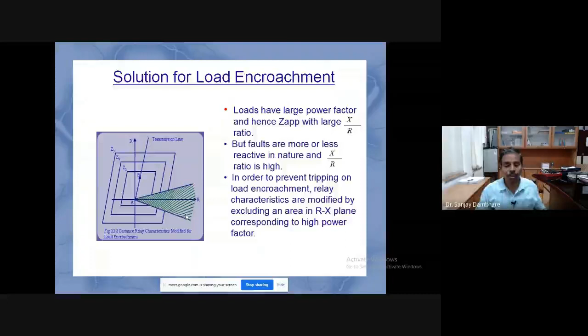So you can see that if the impedance seen by the relay, or the relay trajectory, is coming in this particular area, then it is being chiseled out, and the relay is not allowed to operate in this particular area. While if you consider the fault has very low resistance, and you have a fault loop impedance, so if the fault is occurring, it will put the operating point in this area, and that is how the relay is blocked from operating or maloperating from the load encroachment. Okay.